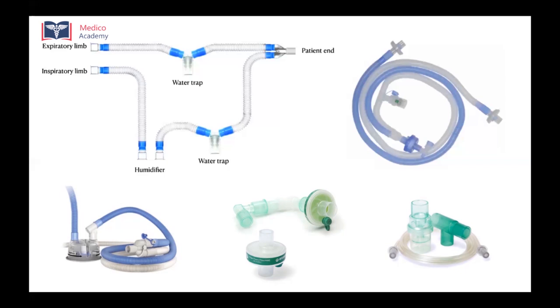So once you connect, you have to basically physically look for any leaks or any holes or damages in the circuit. Most of the disposable ones are single-use ones, and they do not usually have any damages in the circuit. But the reusable circuits, which used to be used previously, which are still being used in some hospitals, you need to check for any tears or cracks or rents in the circuit so that there is no leakage of gases. And also you need to see to it that all these connections at different junctions are tight enough so that there is no loose connection or any unwanted disconnections when you are trying to ventilate the patient. So that's about checking connections and circuits.